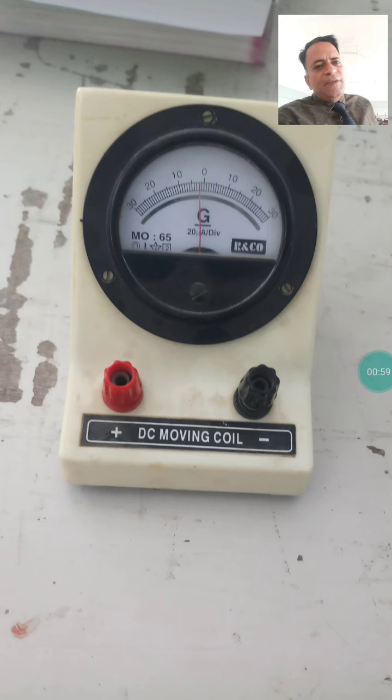See, the moving coil galvanometer is very huge. This is the first disadvantage. Once you pass the current, it will take about 3 to 10 minutes. For 3 to 10 minutes it is going to oscillate and then it is going to give you a stable reading. But in the case of a deadbeat galvanometer, that is this one, it will show you a reading in a flicker, in a very short time. It can show you stable readings.